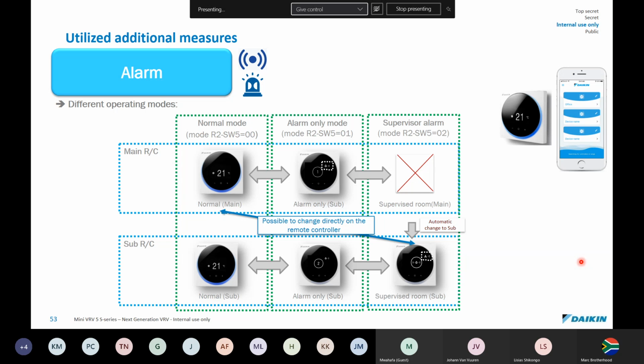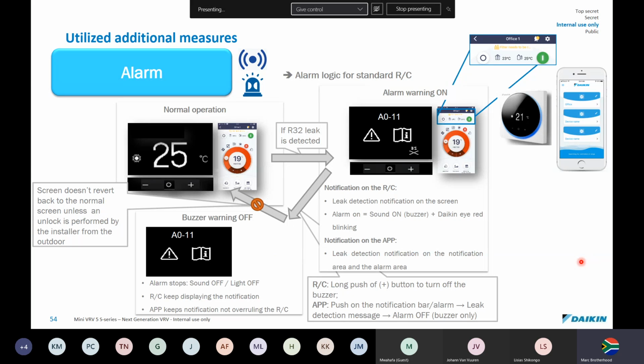I'm not going to go through this with you. Obviously, everything can also be detected on your phone remotely, but this is just the process. If a leak is detected, notification will happen on the remote control. The alarm comes on, the buzzer will sound, and then the Daikin eye will go red. There's also a notification on the Daikin app when you have it on the phone, the leak detection notification. On the notification area and also the alarm area will be highlighted. Then once the alarm stops, the sound is off, the light is off, you'll still have the remote control displaying the notification. And the app on your phone keeps the notification, so it won't overrule the remote control.